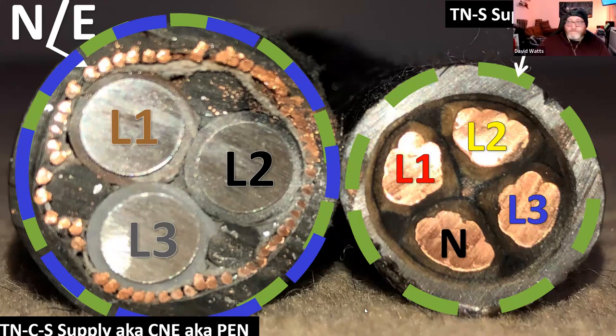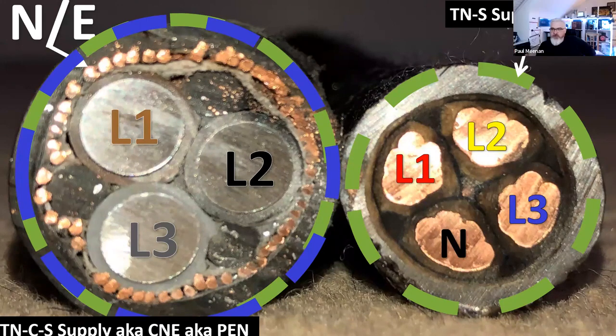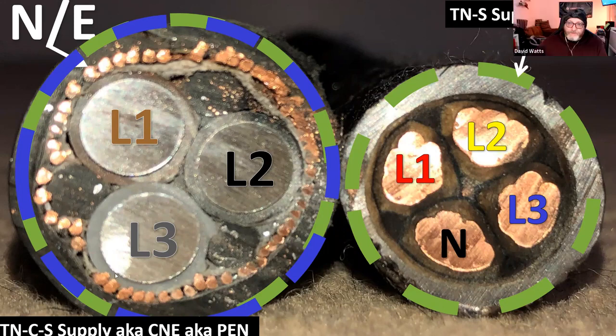And the main reason it gave was purely that it was a cost-saving cable, which gave greater value to the networks, which was fantastic. As we know, we talk about the whole life approach, the life cycle of the cable - what happens if it fails, because obviously that little bit of copper on the left there, if that breaks completely, you then have what is known as a broken PEN, which in your installation, if you switch on, you potentially can have 240 volts in your metalwork, or you will really.